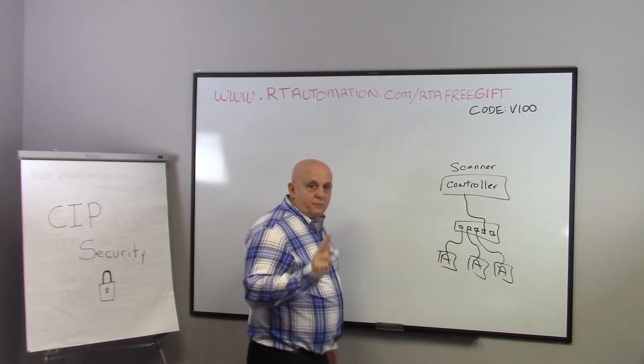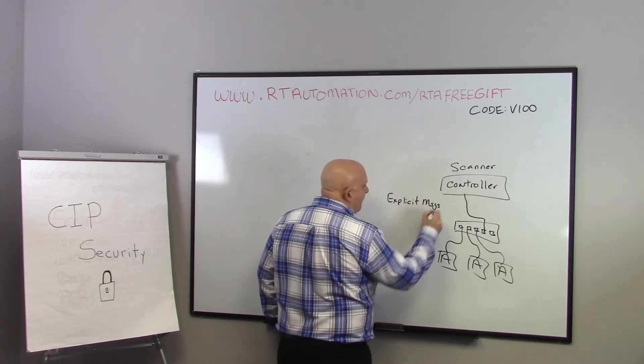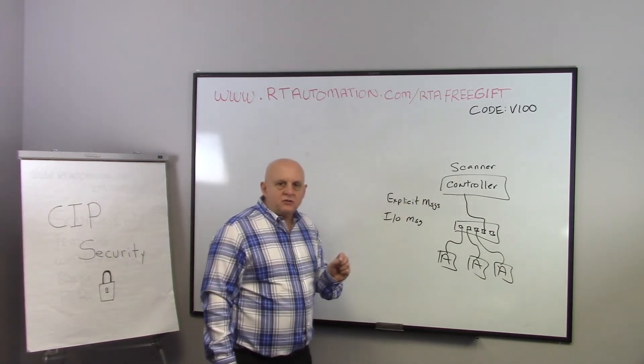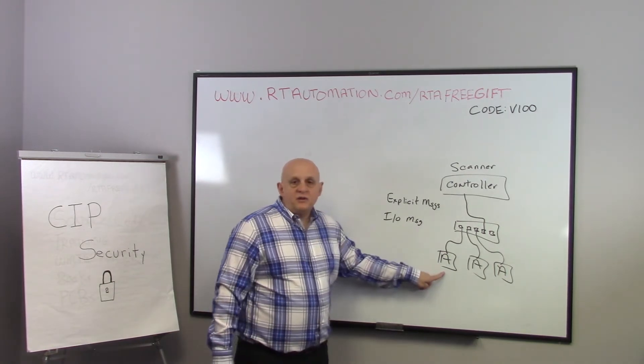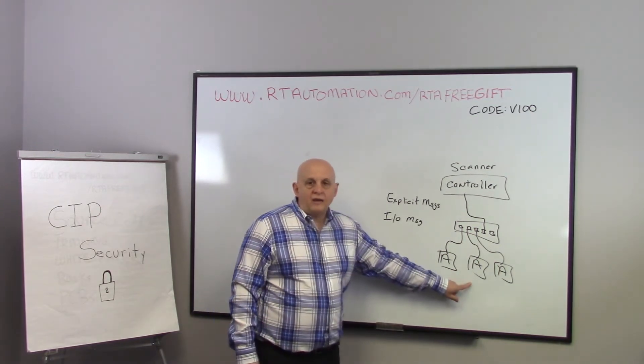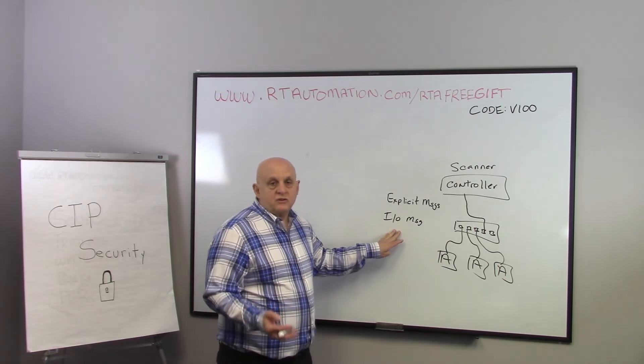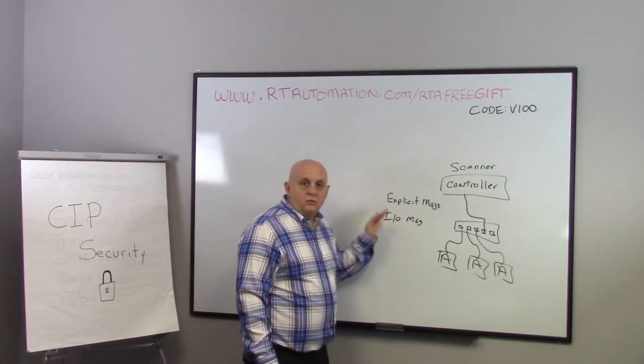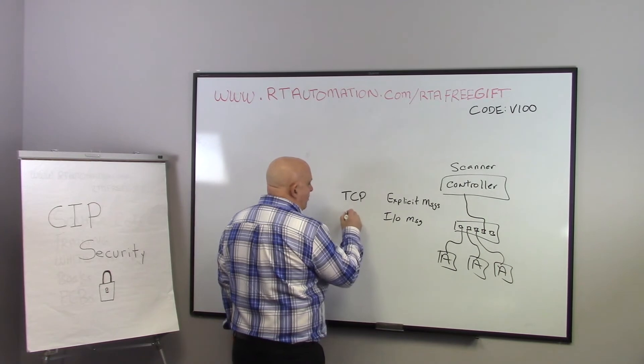There are two kinds of messages that go across that network: explicit messages and IO messages. The controller or PC sends an explicit message when reading or sending information — for example, how many cycles has this valve completed, or telling a drive to change the ramp-up time from 10 seconds to 12 seconds. An IO message is inputs from adapters going back to the controller and outputs from the controller back to the adapter. EtherNet/IP uses two different transports: explicit messages use TCP and IO messages use UDP.